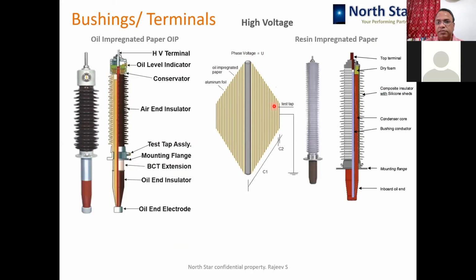The second development is resin impregnated paper kind of bushings, where there is no oil. In an OIP bushing, you have a small conservator at the top, which is filled with oil, and the paper is soaked in the oil. This conservator keeps replenishing the oil and keeping the paper wet. This causes several issues, like leaking of the oil, or, because there is an air seal, moisture goes inside, leading to different kinds of issues.